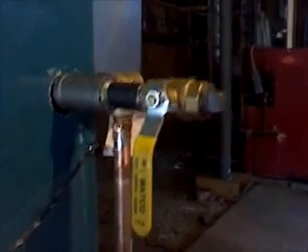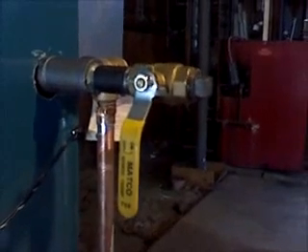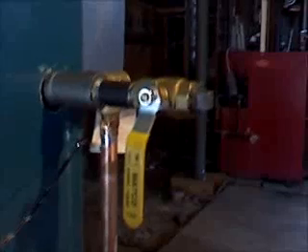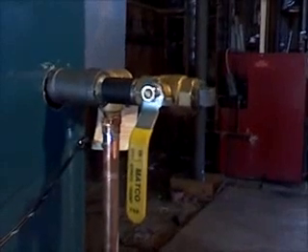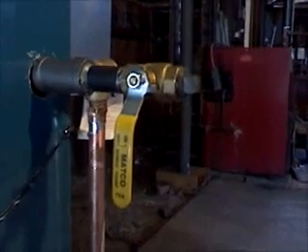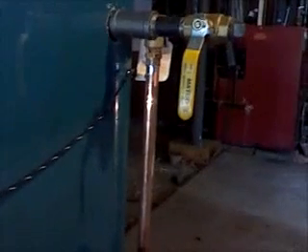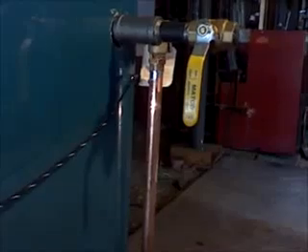Steam boilers are very dirty. Especially when you're doing a replacement, a lot of the cutting oil from the installation and a lot of the dirt from the system needs to be cleaned out of the system. But if you use some of the chemicals, it will make the problem worse. It will bring all the junk out of the pipes back to the boiler. So the best way to clean the steam boiler is to just continually fill it and drain it. But you have to be careful, because if you add too much cold water too fast to a steam boiler, you can crack the cast iron.